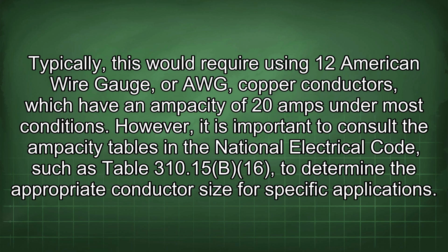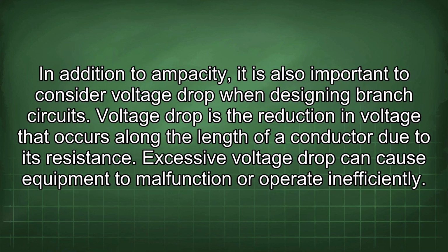Typically, this would require using 12 American Wire Gauge, or AWG, copper conductors, which have an ampacity of 20 amps under most conditions. However, it is important to consult the ampacity tables in the National Electrical Code, such as Table 310.15(B)(16), to determine the appropriate conductor size for specific applications. In addition to ampacity, it is also important to consider voltage drop when designing branch circuits.